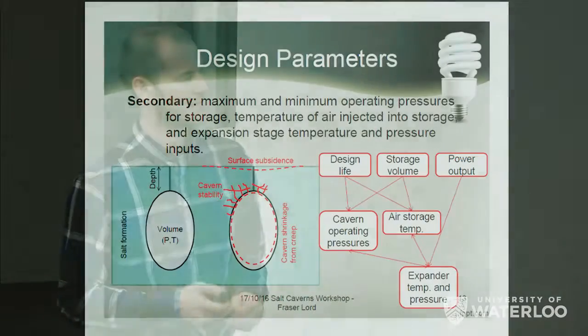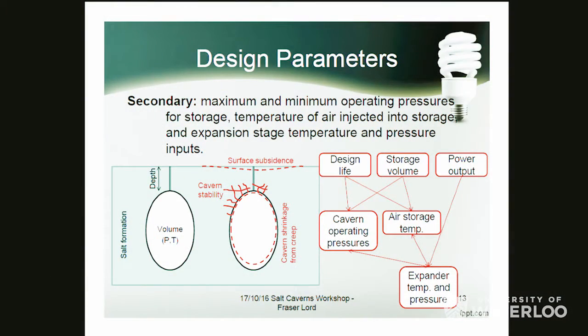Following from the primary design parameters, I selected secondary design parameters most critical to project success — generally in terms of achieving your power output, which is governed mostly by expander temperature and pressure inputs, within the limitations of both the turbomachinery and the cavern's operating ability. To avoid risks such as cavern stability, ground surface subsidence, and excessive cavern volume loss from creep, you need to carefully consider your operating pressures and temperatures.